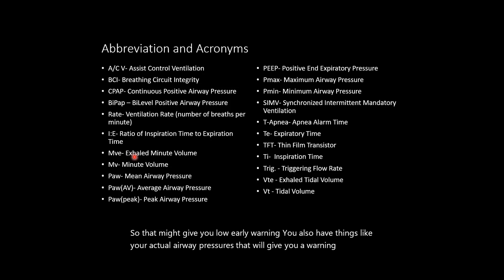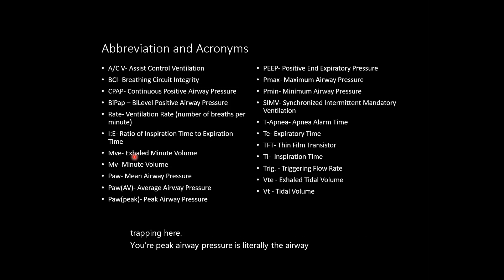You also have things like your actual airway pressures that will give you a warning, and what we call plateau pressures and stuff like that, that we won't get into too much today, that can also give you a warning that you're trapping air. Your peak airway pressure is literally the airway pressure in the ET tube. So if it builds up, what that tells you is that you're trapping air, or that there's something else that is meaning you're having to ventilate at higher rates. Now, sometimes that isn't just trapping air. That's because you have sick, non-compliant lungs as well.